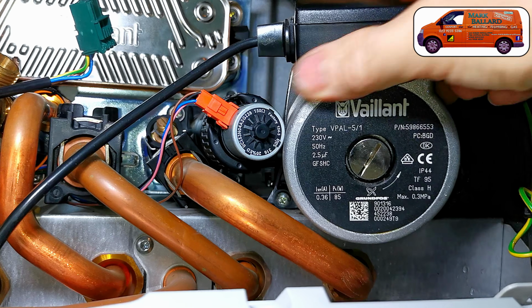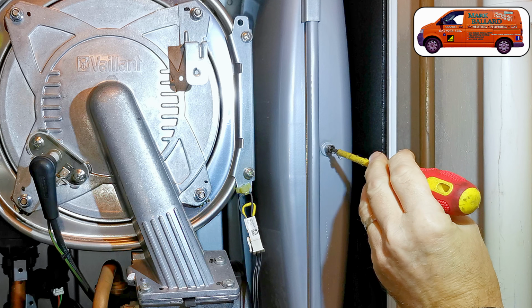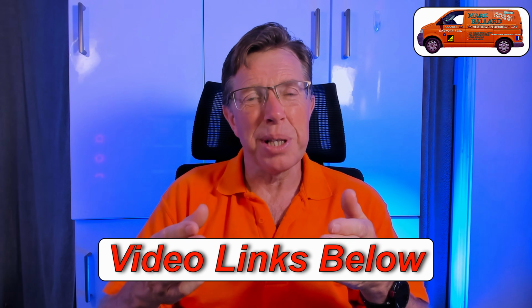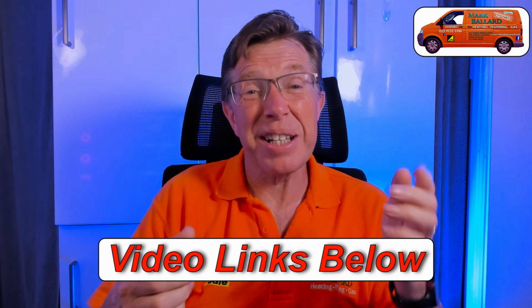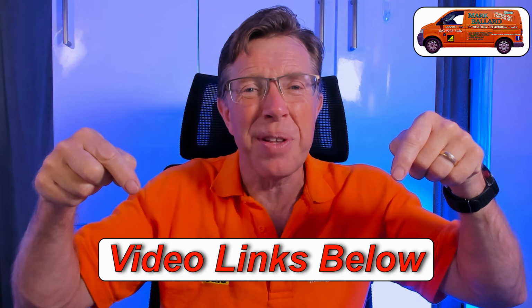If you have a Glowworm boiler, then this video will help you as well, because Glowworm use the same pressure sensor. Now, the F75 fault is not always caused by your pressure sensor. It could be because you've got a faulty pump, a faulty pressure vessel, or maybe just a capacitor has gone inside your pump. And of course, I've made videos all about how I go about replacing all these parts.